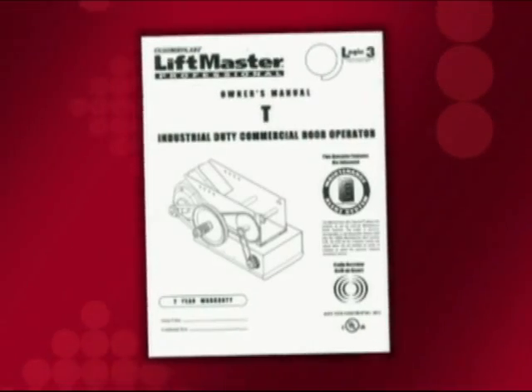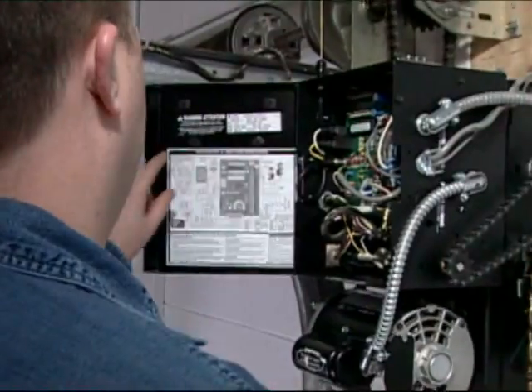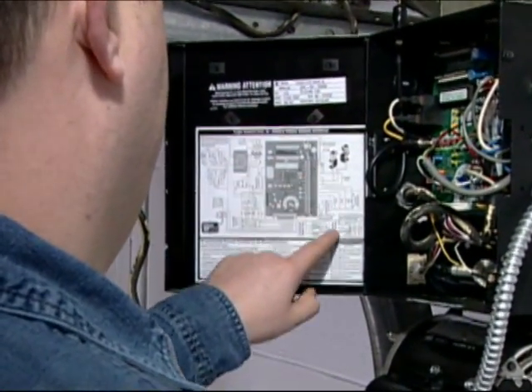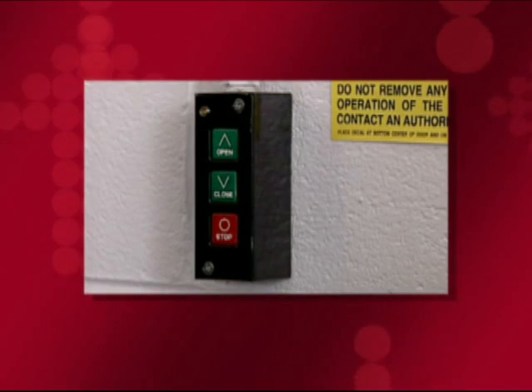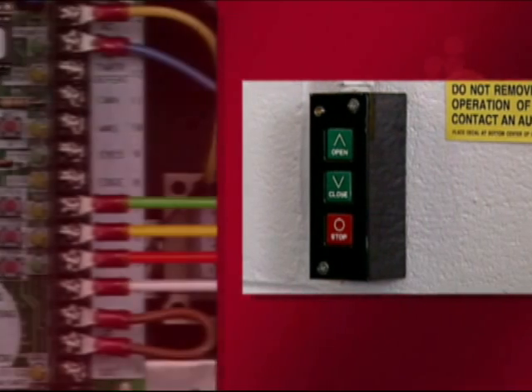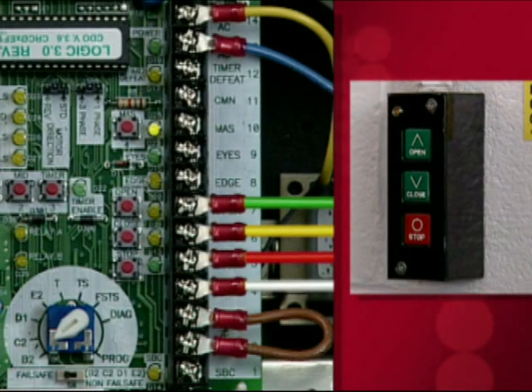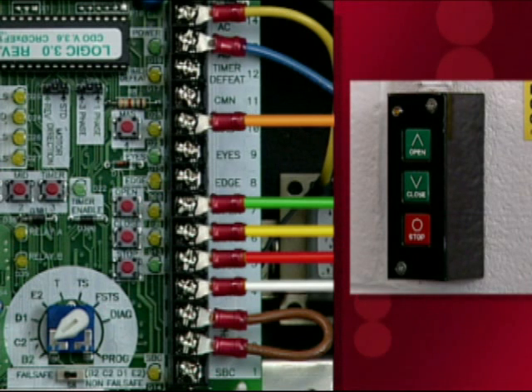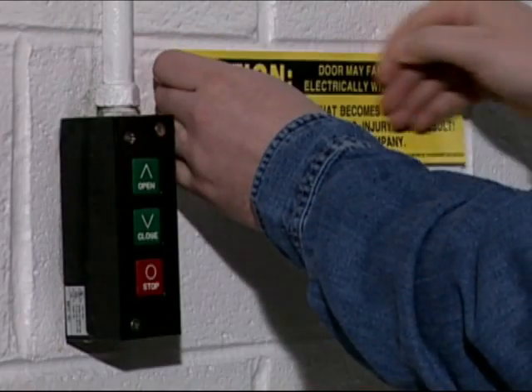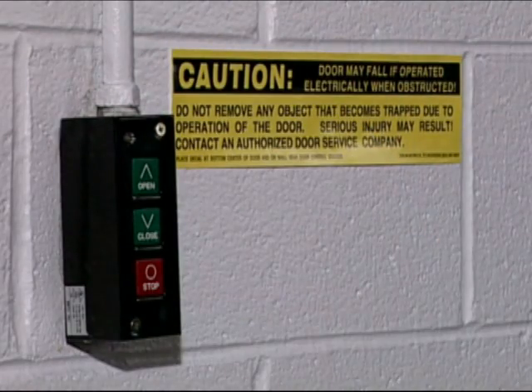A guide to error codes can be found in the owner's manual and on the inside cover of the operator. In order for the 3-button control station to blink error codes for troubleshooting and routine maintenance, a 5th wire must be run from the MAS input on the low-voltage terminal strip to the 3-button control station. It is always important to make sure that safety warnings are clearly marked with caution and warning signs.